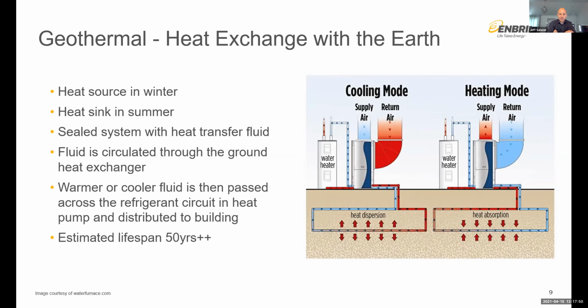These heat exchangers are made of polyethylene piping. Typically, there are a number of different materials that have been used in the past, but polyethylene is the most common used product currently, and it has a lifespan of well in excess of 50 years. So I have systems that I've been working on that were installed as of the early 80s. So they're pushing 40 years old, and there's no degradation of that piping asset. It's a very robust pipe.